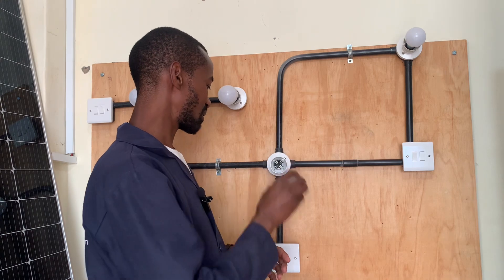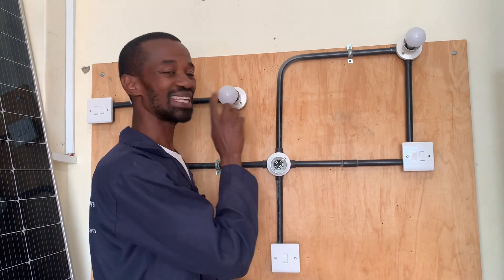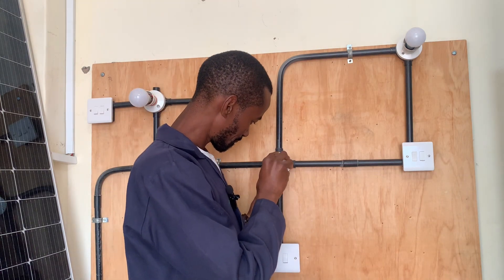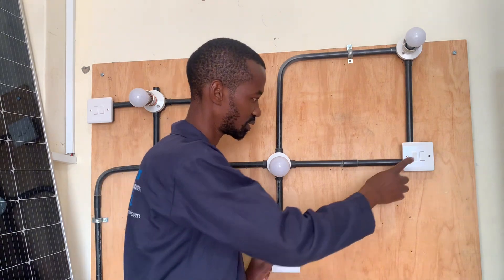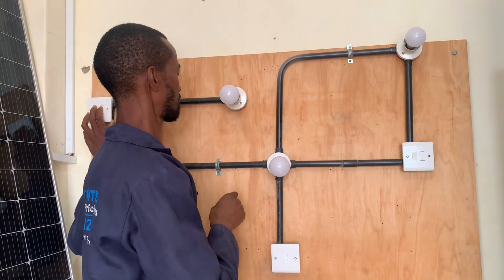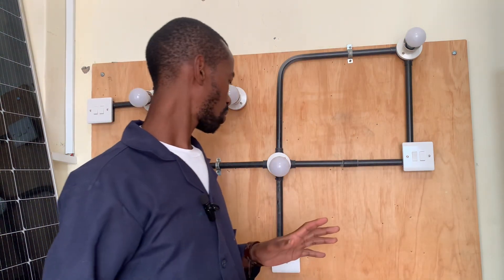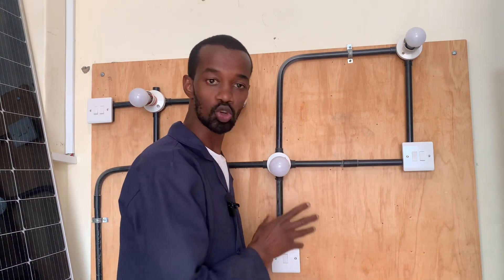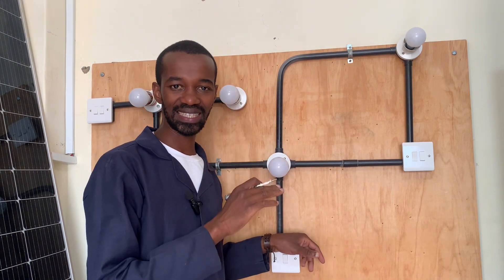I simply start by removing this one and I can see everything is okay in my bulb holder. Since this one is working properly, I will take that bulb and use it here. It is still not working. The other ones are still working. If I take this working bulb here and it also works in another position, my conclusion is that the wiring on this particular bulb point is not working. What I will do is switch off the circuit breaker at the consumer unit — the one that activates the lights in that house.